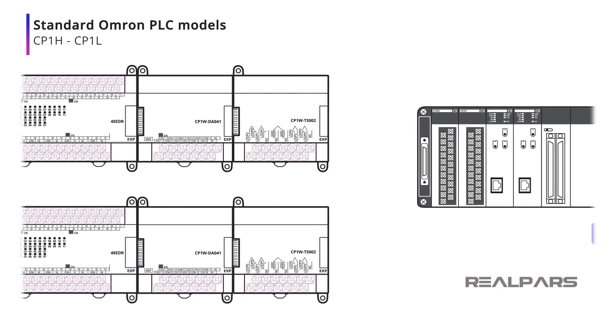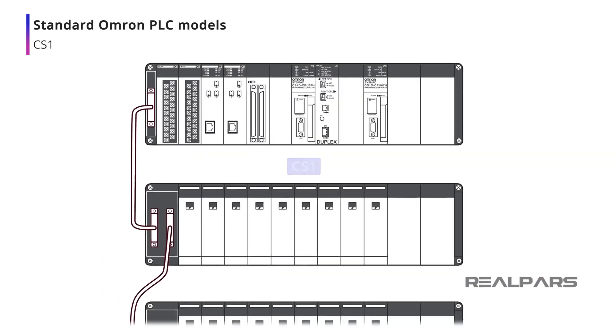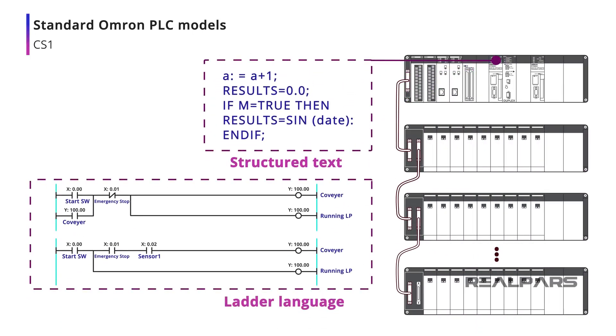For larger systems, the CS1 CPU has a maximum capacity of over 5000 digital I/O points over seven expansion racks. Any combination of up to 80 I/O modules and communication modules can be mounted in any position in the I/O racks. The CS1 allows the use of IEC standard structured text and ladder language, which allows flexibility in how programs are written.